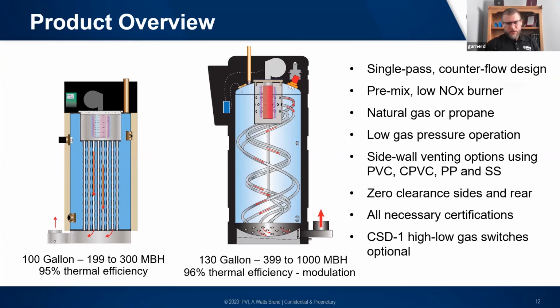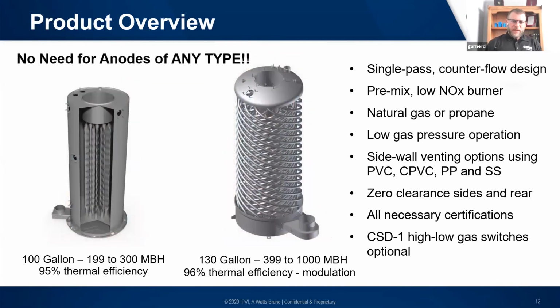The 100-gallon tanks are just straight tubes. The 130-gallon tanks, we have kind of a coil going in there to give us increased surface area for the heat transfer. They're available propane, natural gas. We can vent in all the common materials, PVC, CPVC, and they have 0 side clearance. Heat exchangers, I probably said, duplex stainless steel. We do not need any anodes of any type, which is a huge advantage, because even with the electronic anodes, unless everything's in the line of sight of that anode, it's not going to protect the heat exchanger on that unit.